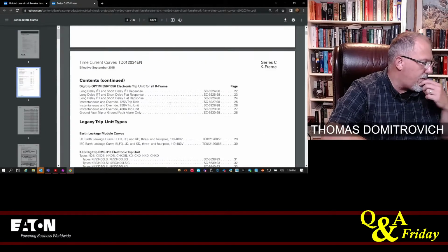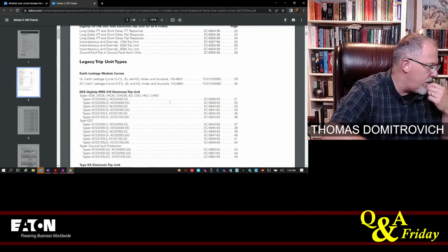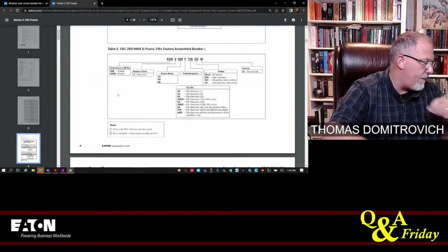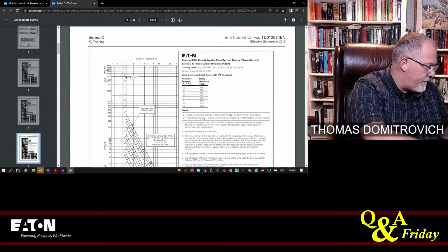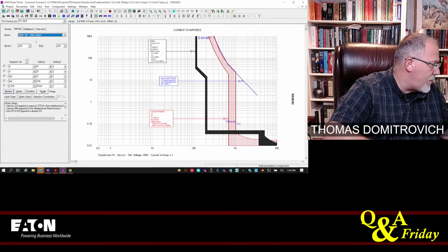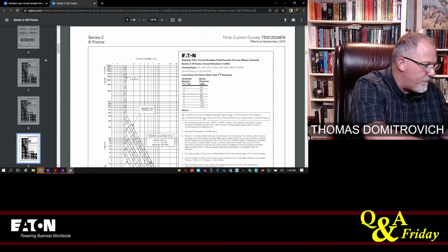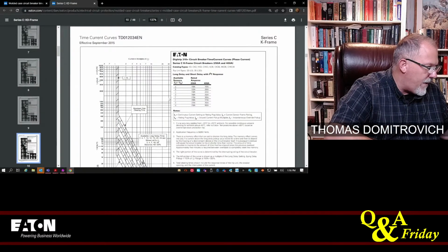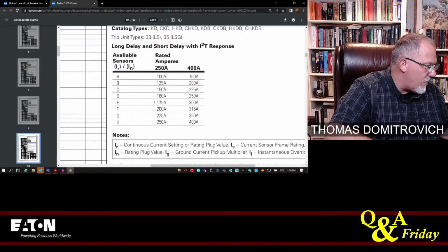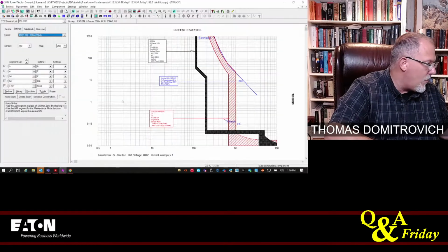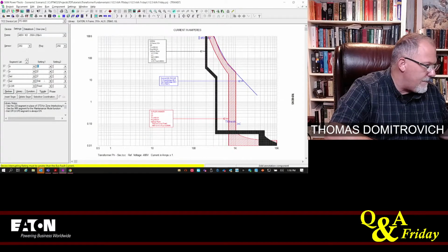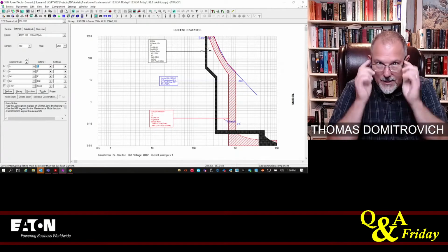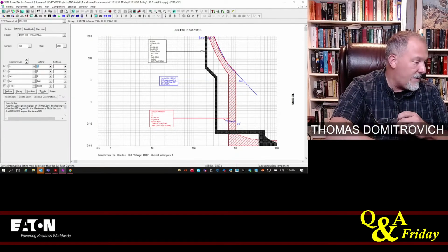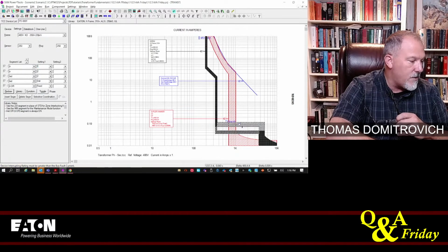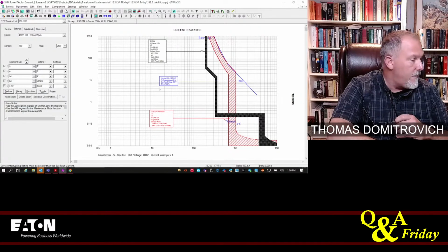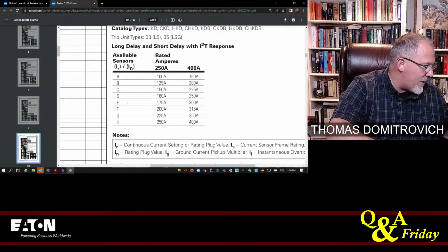So I need a 310+, right? 310. Okay. I have 250 amp frame. Here's a 250. These are my settings. Well, I can even do 175 if I put it on E or F. So here is E. So I could change the size of my conductor. I could put a smaller conductor and still not worry about my instantaneous, my inrush. So E was 175.